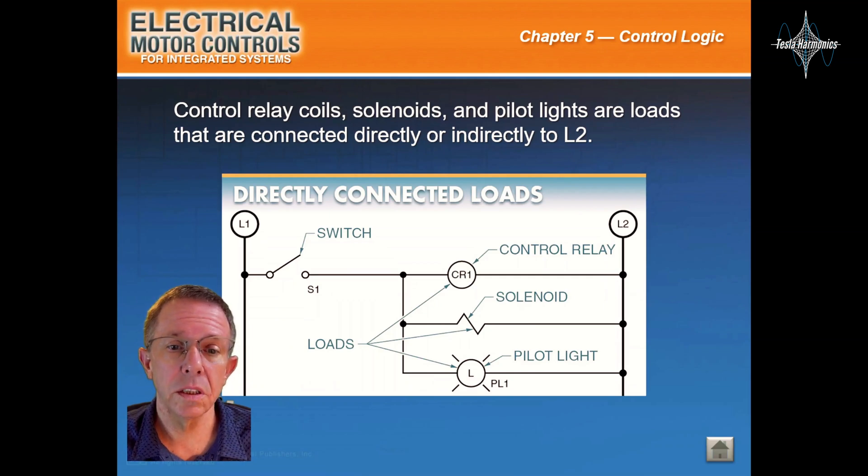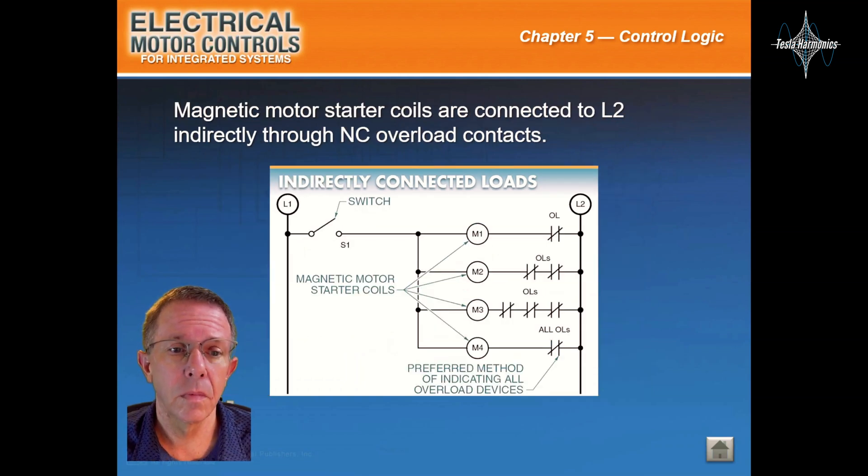Control relay coils, solenoids, and pilot lights are loads that are connected directly or indirectly to line 2. Magnetic motor starter coils are connected to line 2 indirectly through normally closed overload contacts.